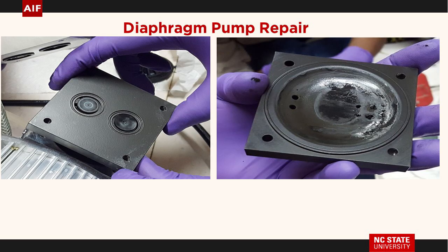After so many back and forths, the rubber tends to break. So it doesn't work anymore. You can get rebuild kits and take care of those. Depends on how often you use it, how much you're doing it. They suggest about 1 year. Actually, the one on the XPS has been running for probably 10 years and hasn't been changed.